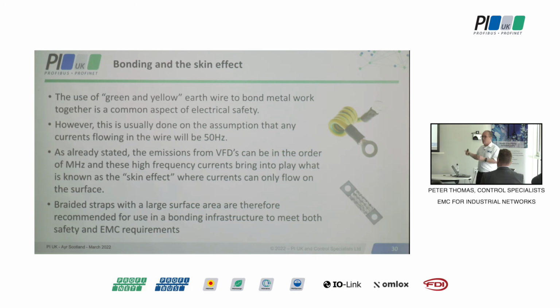But we're now living in a world where we've got higher frequency currents, possibly in the order of megahertz. Now it's a different world. When we try to put the same amplitude of current through a conductor, it will flow on the surface. It's literally not possible for the electrons that make up the current to flow in the middle. So whenever the current comes to something like a green and yellow wire, it's going to be a relatively high impedance, and it's going to try and take an alternative route back to its source, which it often does. So this is why, for bonding, braided straps are recommended, because they've got a bigger surface area. These are good for electrical safety, and they're good for EMC as well.